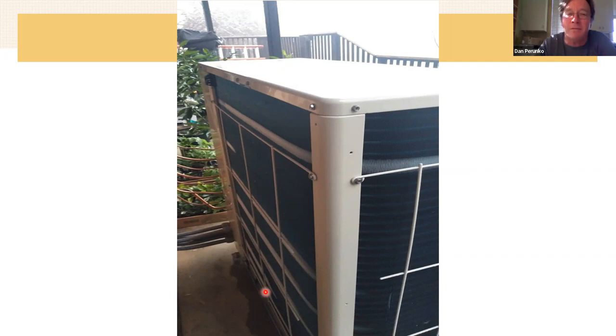And the other thing you can tell from this photo is this is a variable capacity heat pump. The way that you can tell is it has this great big coil and only a little bit of it has frost on it. So the machine's not doing a lot of work right now, right? And the variable capacity machines have much higher efficiency and are one of our most important improvements that have been made in heat pump technology in the last, I don't know how many years.